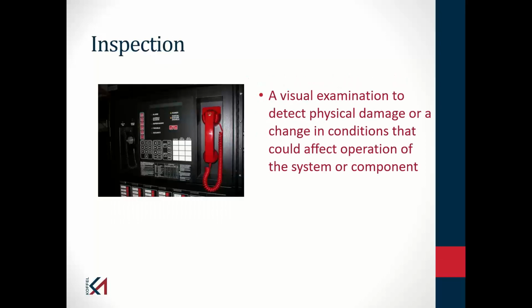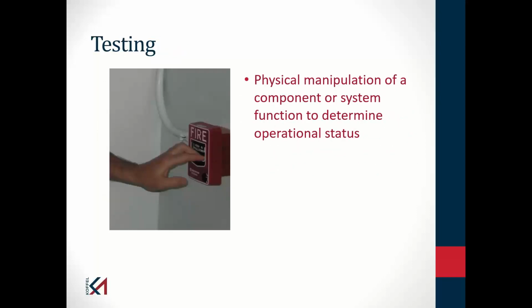Now, as much as I said many of us can do an inspection activity, many of us are going to be limited as to what testing activities we will perform. If my insurance carrier were on this call, he would hope that I would tell you we don't do any test activity, because it just poses some liability that as an engineering firm, we really should not be absorbing. And if I were to flow water in your system and a coupling failed, I don't have the ability to help you get that system back in service.